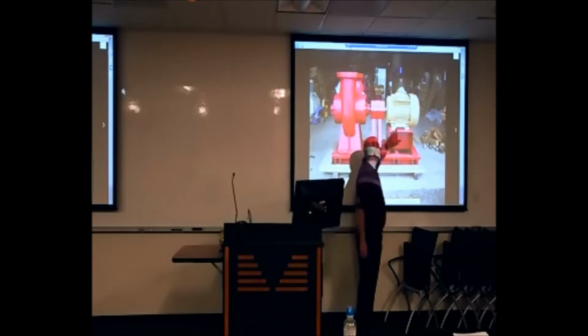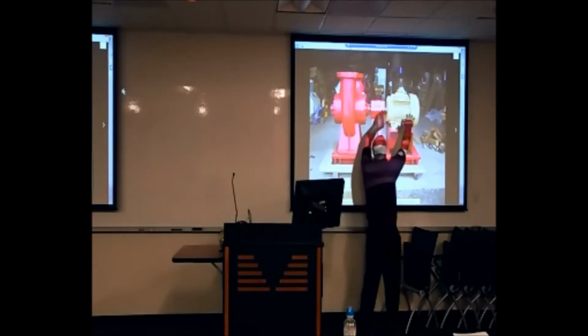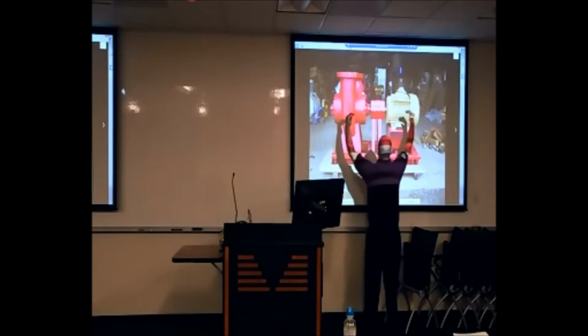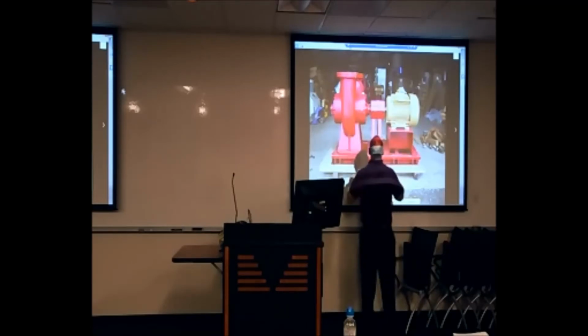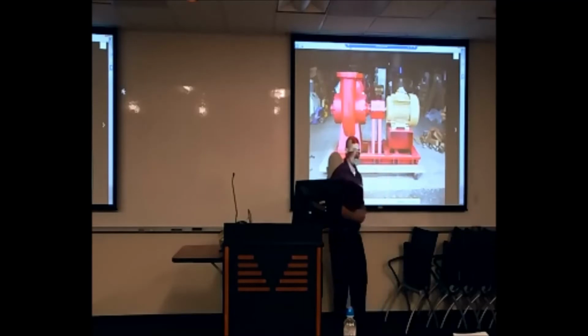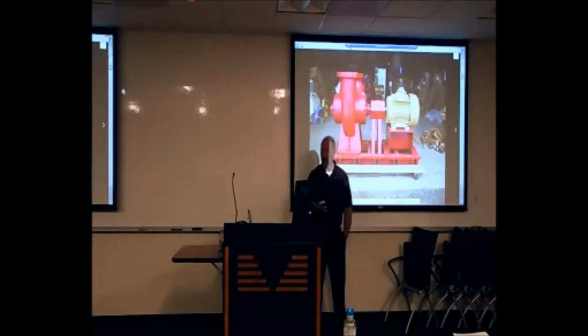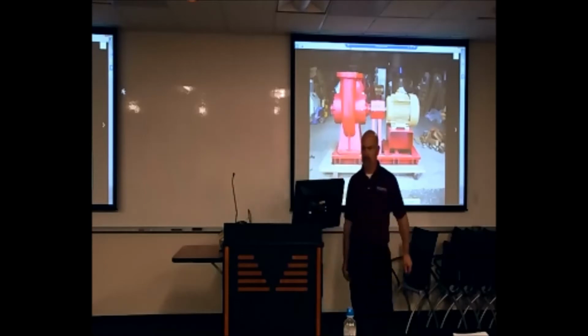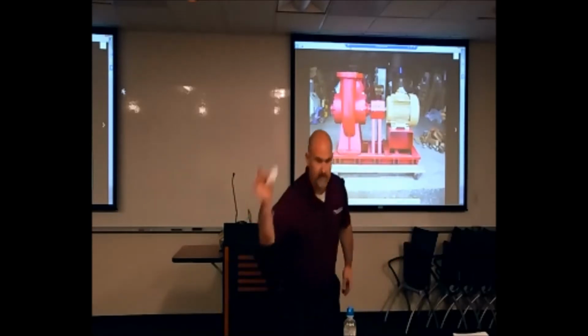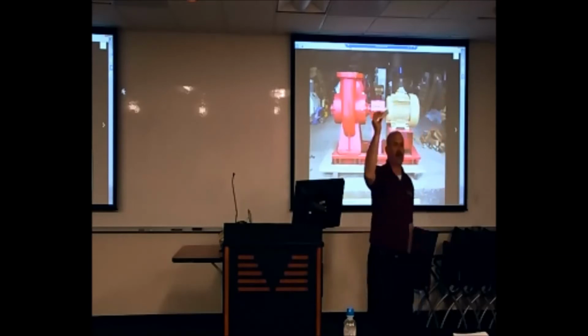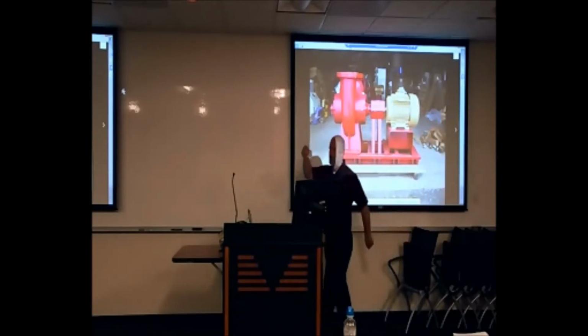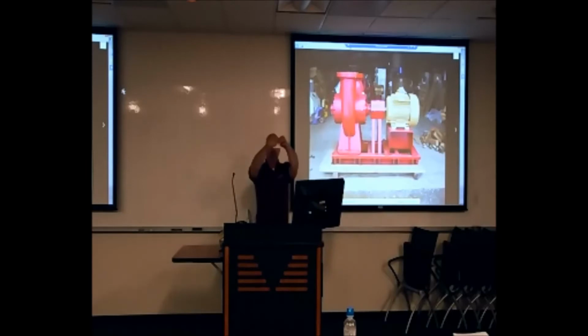You can see there's shims located under this motor. These shims are used to raise, lower, and move this motor around so that we are in perfect alignment with the pump end. To do the alignment, we don't really require any special tools. I'm going to show you my pump alignment tool. A credit card, business card, any flat piece of material can be laid across the coupler, and you're looking for any sort of misalignment, tilting type of thing. It really just needs to be a straight edge alignment. We don't require laser alignment or dial indicator alignment on this type of coupler.